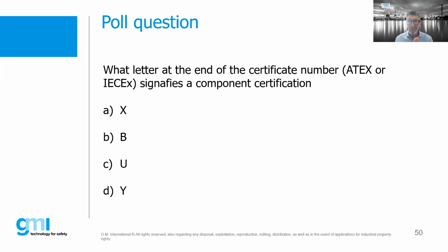We talked about X, but in a different context. That's right. Every certificate will have either an X, a U, or no letter at all. An X means a special condition for safe use. A U means it's a component certificate. If there's no letter at the end, it's assumed we can install it according to the manufacturer's documentation and the standards.